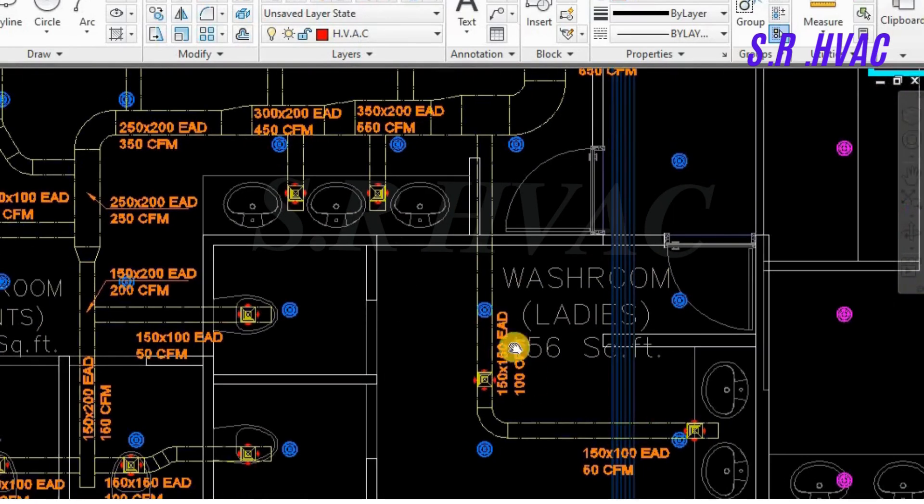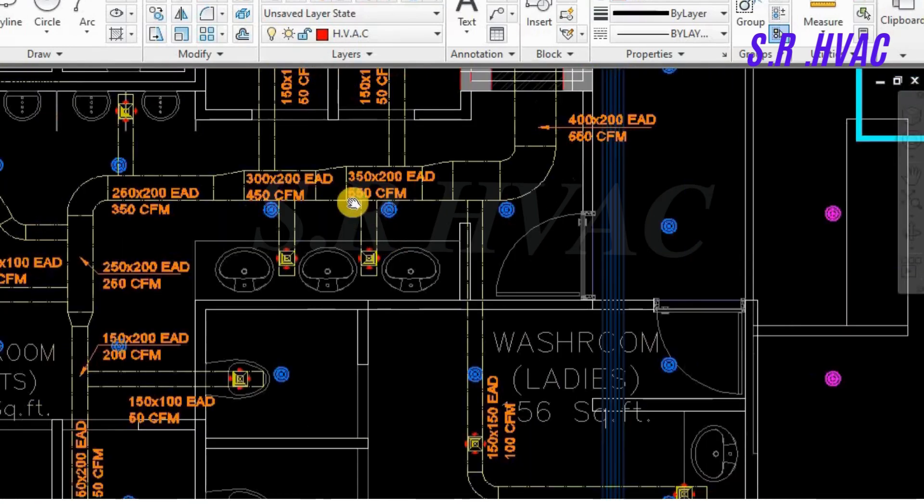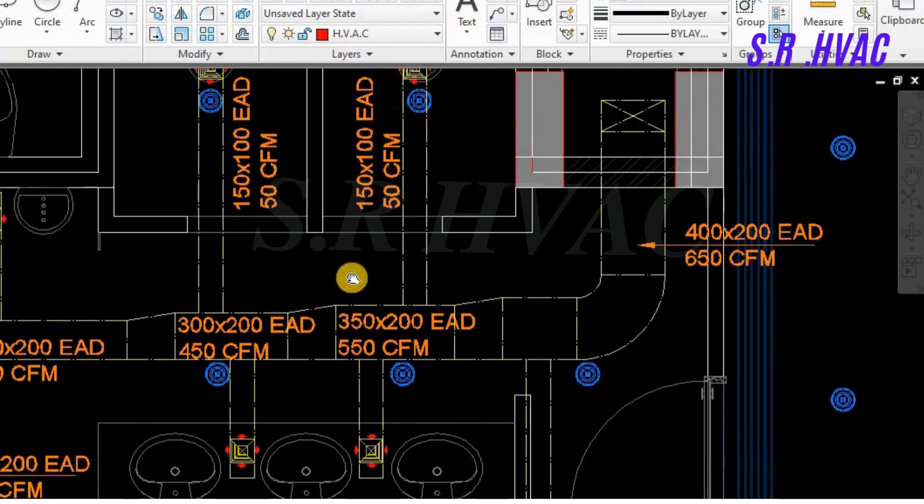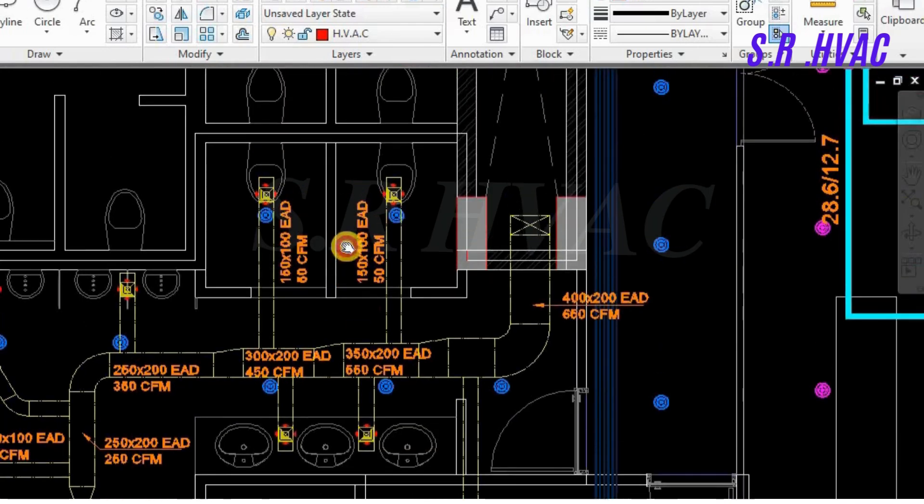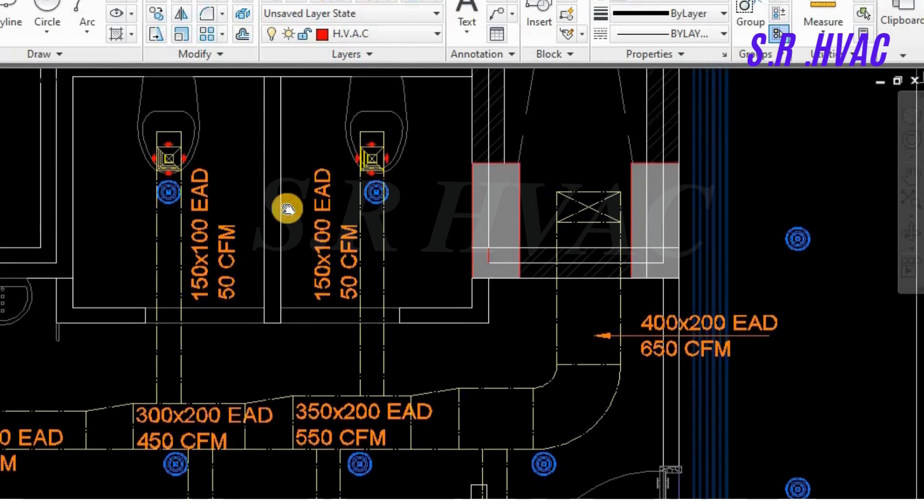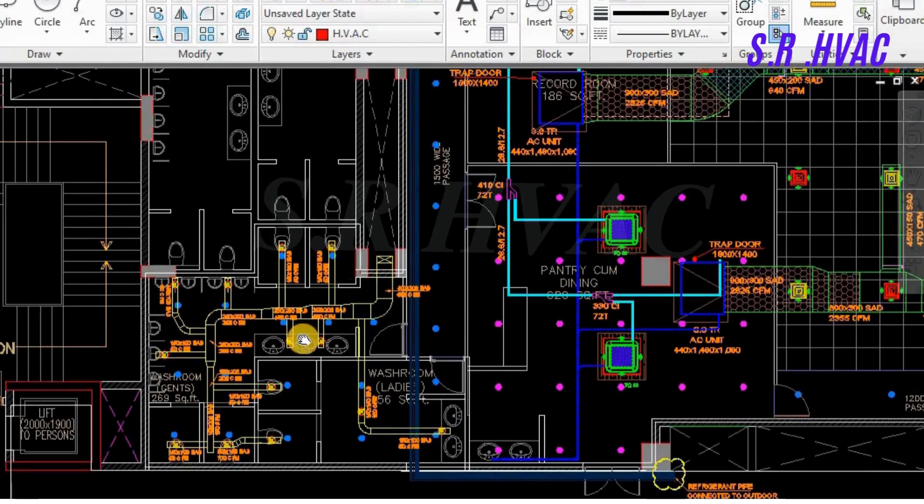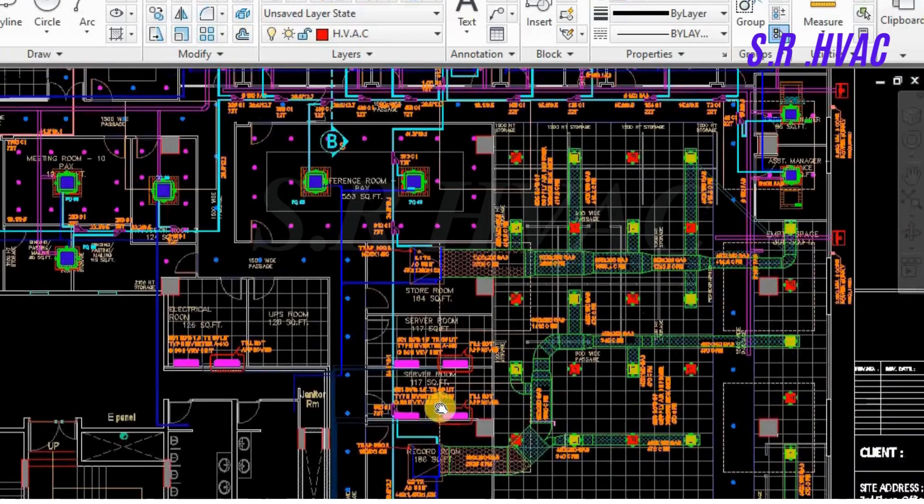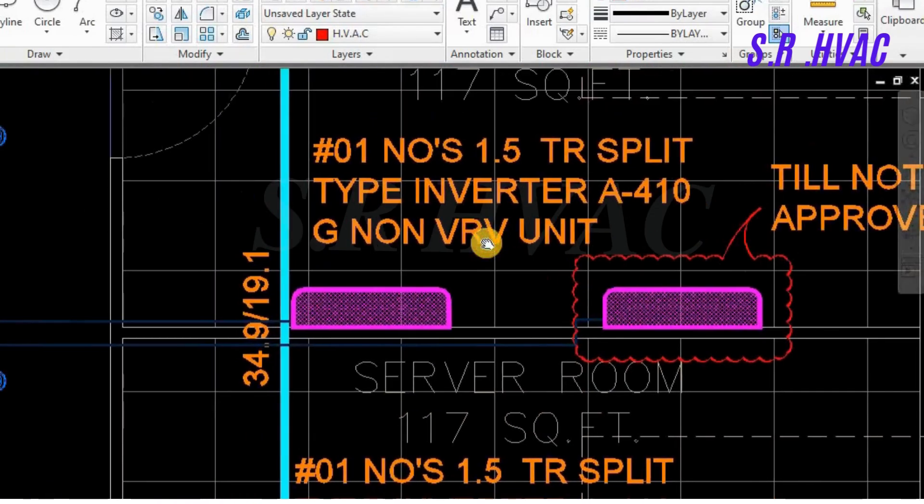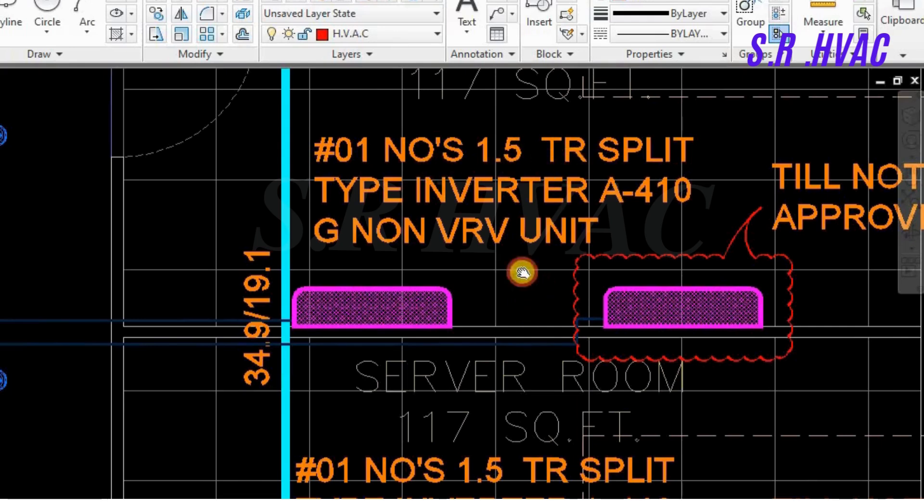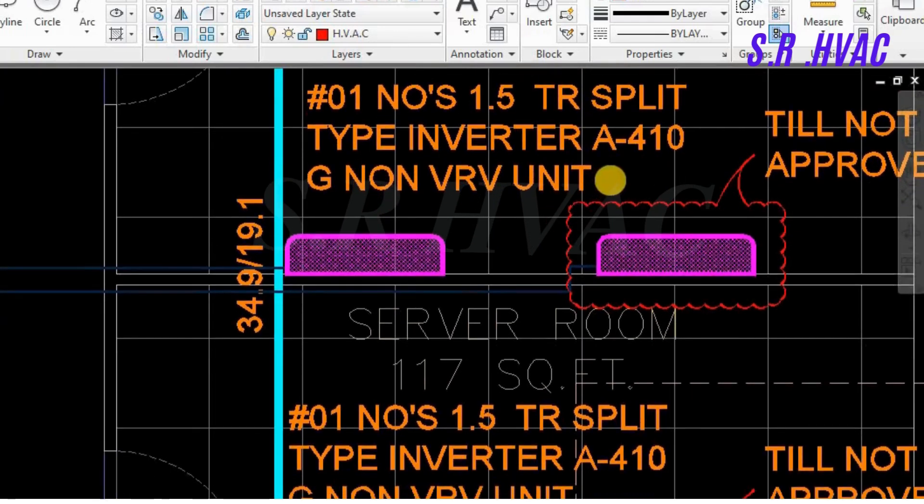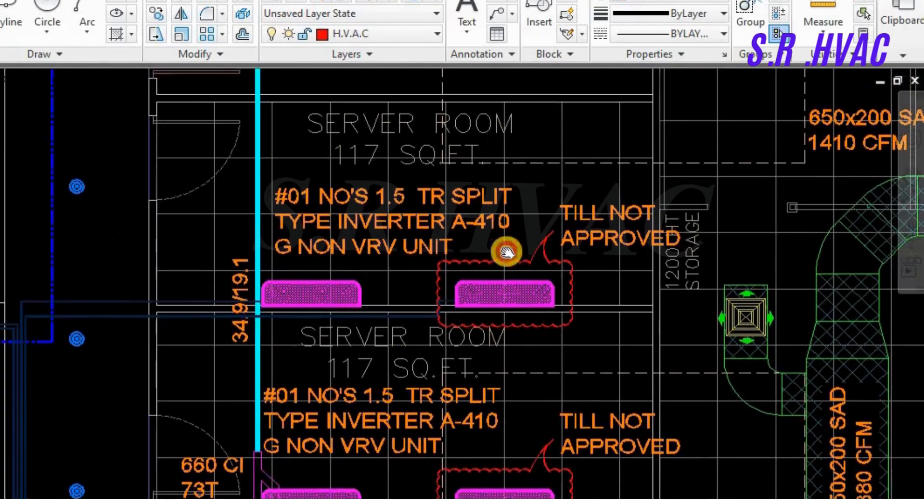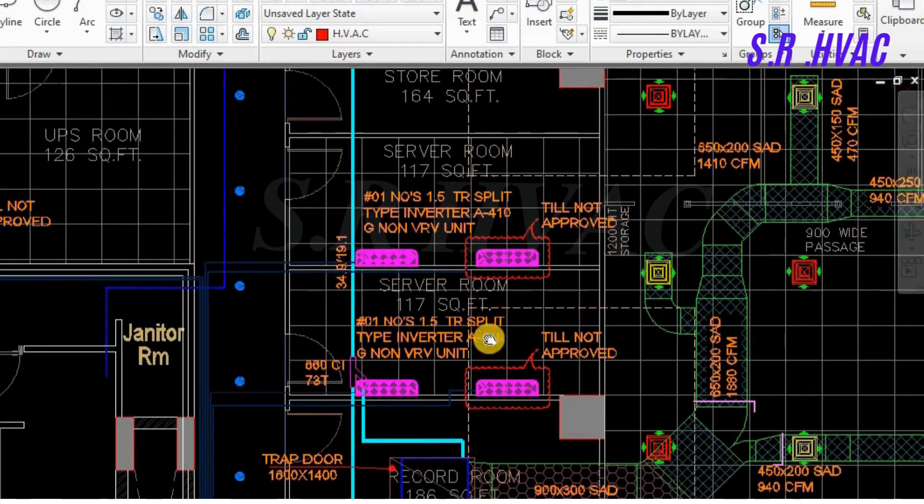This is the gents set, this is the ladies set. This is all our exhaust air duct, EAD 150 by 100. Friends, this is exhaust air duct. So this, you can see this is the inverter, this is not connected to the VRV. This is 1.5 split inverter, 410 is the gas, non-VRV unit. And there are two already placed in this room and one is still not approved. We have to get it approved before doing this. This is the server room of 117 square feet.